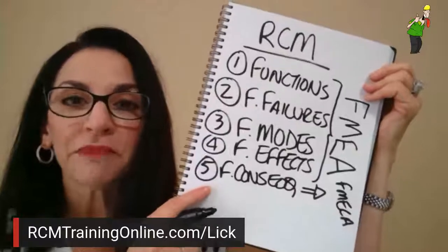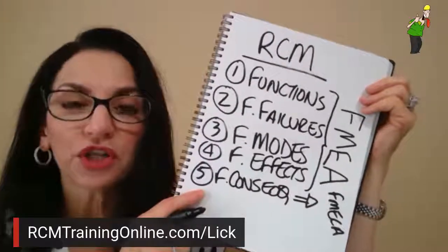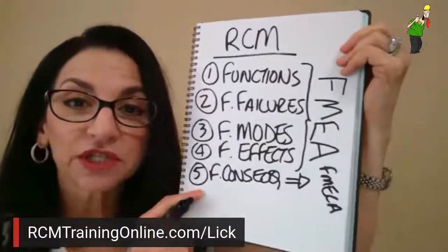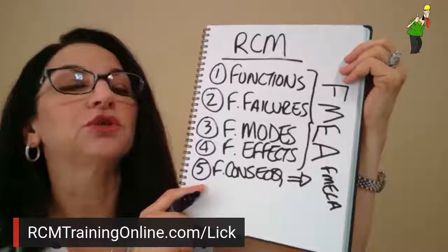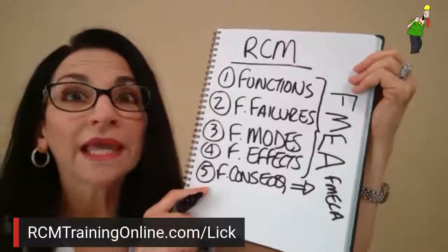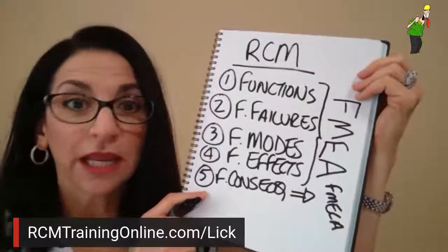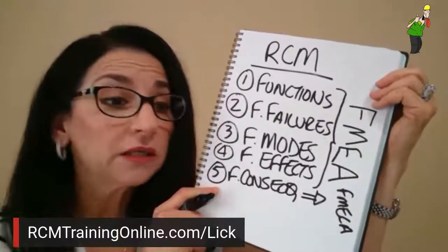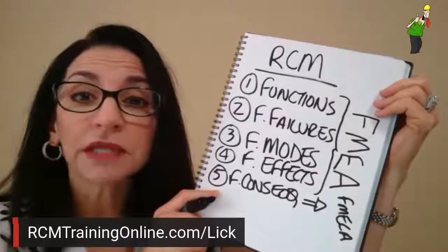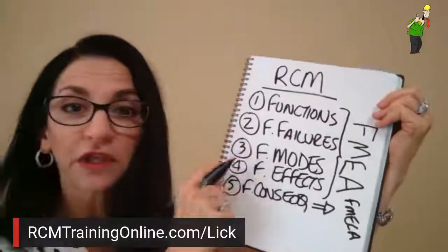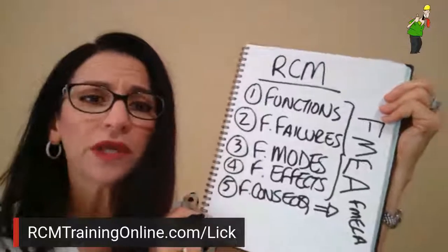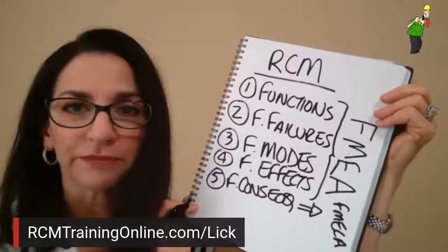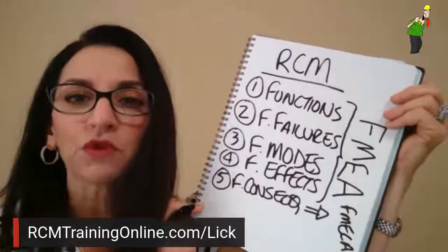Once you do your FMEA, you put it through the guts of the RCM analysis — the RCM decision diagram. That's when you decide: am I going to do preventive maintenance? Am I going to do condition-based maintenance? Or am I going to apply a default strategy? That includes deciding 'no scheduled maintenance' for certain failure modes. We don't do something for every failure mode — there are tons of failure modes that we simply run to failure.